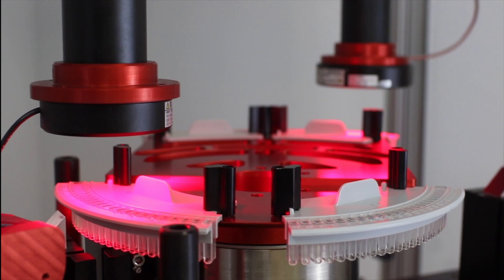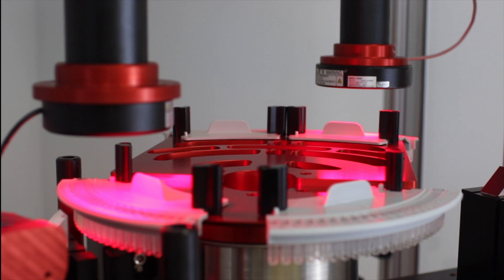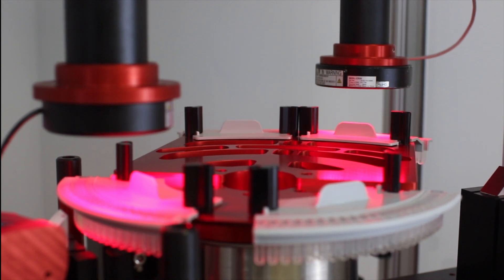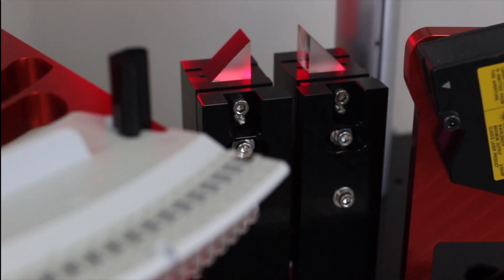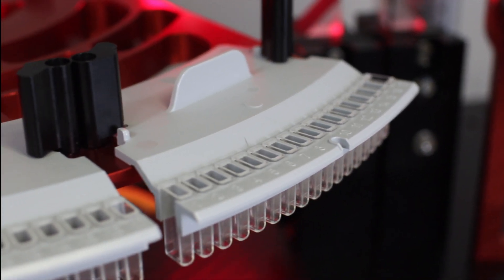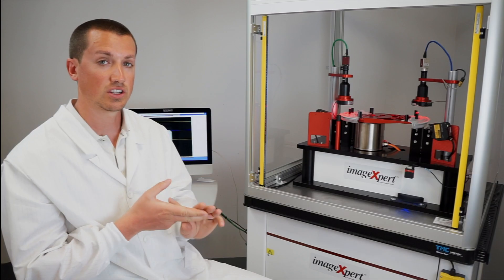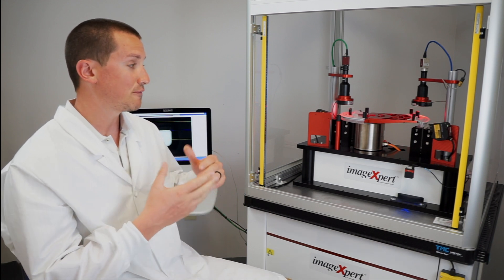The cuvette moves to the second inspection position, where a dual camera and lighting setup inspects the window from both sides of the cuvette. It checks the thickness of the windows, the orientation of the part, in five degrees of freedom.